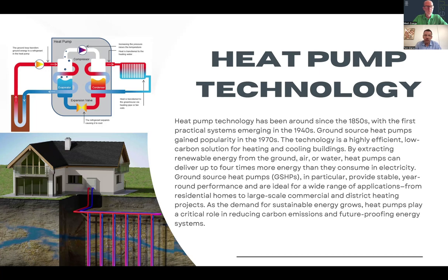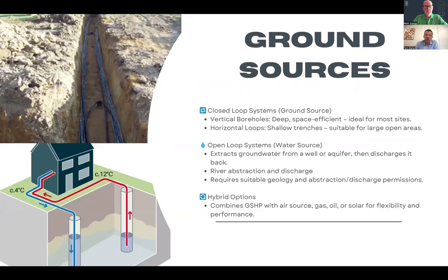Some of them have this option built in, and with some you have to install additional heat exchangers outside. But the technology is moving forward, and this is becoming more and more popular with properties. As I said earlier, we've got a few different types of technology. It's the same heat pump, but you're extracting the heat from different sources. In the top left picture, you can see the boreholes, the borehole tops, and then horizontal pipes linking the boreholes with the manifold. This is considered a closed loop system. And depending on the demand of the property for heating, hot water, pool, you might have from one borehole to 50 or even more. That depends on the demand.